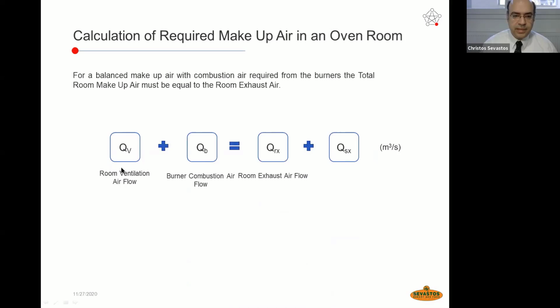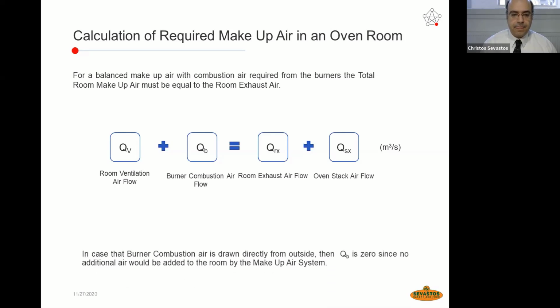What does this equation mean? Room ventilation airflow plus the burner combustion airflow should be equal to the room exhaust airflow plus the oven stack airflow. This is the mass balance based on which we can calculate and define the proper ventilation airflow in areas where we are going to have tunnel ovens.